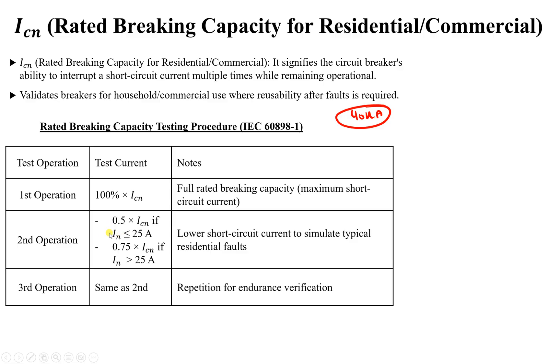The third test repeats the same operation as the second. So the full procedure is: 100% of the fault, then a reduced fault level, then repeat — three interruptions in total. This confirms the breaker under IEC 60898-1 can handle repeated faults and remain operational.